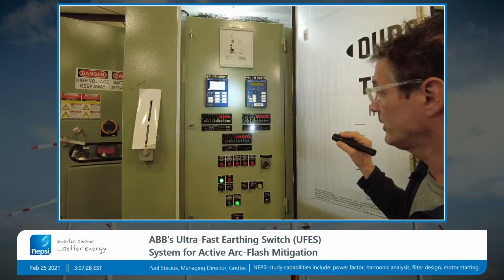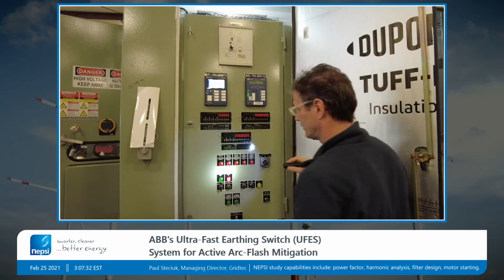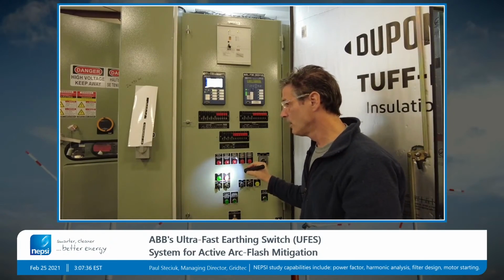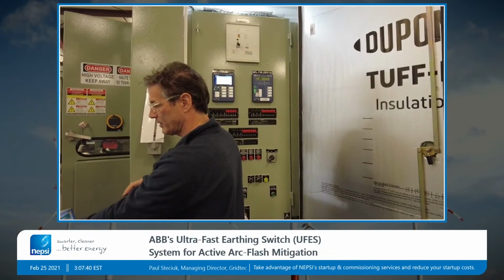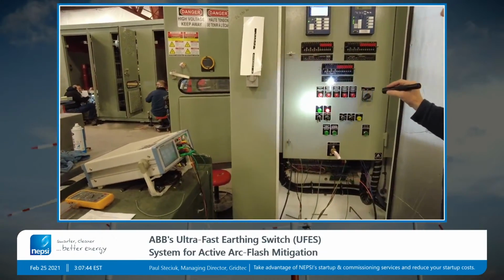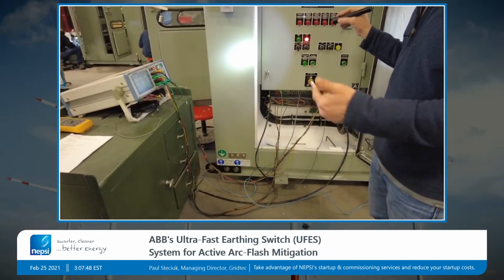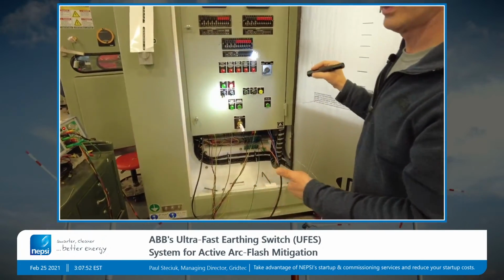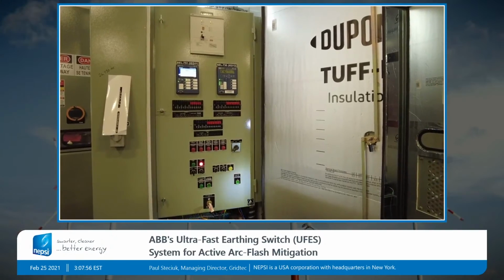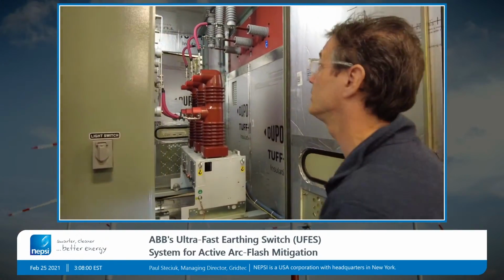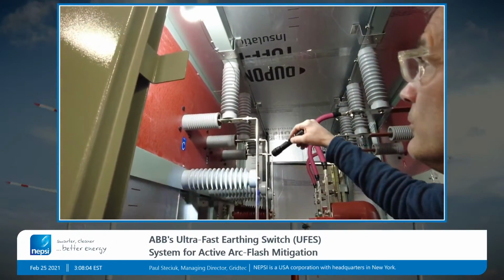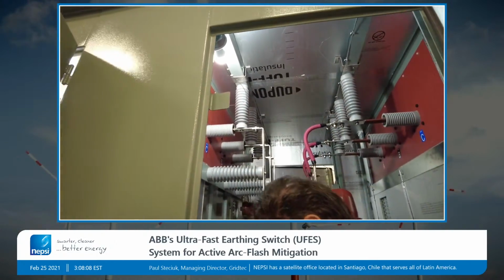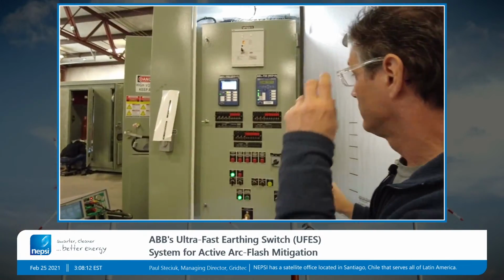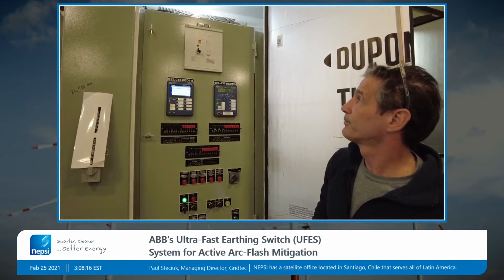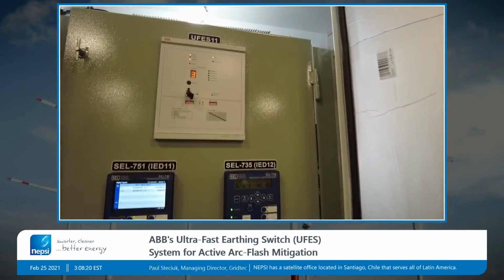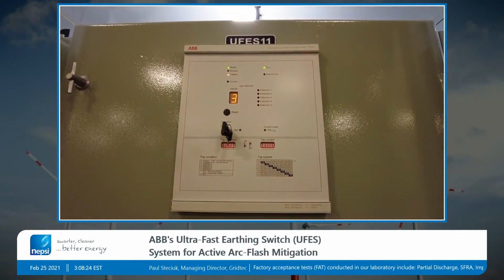Do a sample test. For testing, we'll just close the circuit breaker. You can hear the circuit breaker close. We generally input a current into the bank here. So we have a current injection going into the bank, and the relay has to see both current and light. Right now the bank is seeing current, and if we want to activate a light source, we can do that with a flashlight. I'm going to put it up to the source here, and there was a fault inside the breaker compartment. The neat part about this is you can see the light sensor number 3 picked up, so you know where the fault took place.